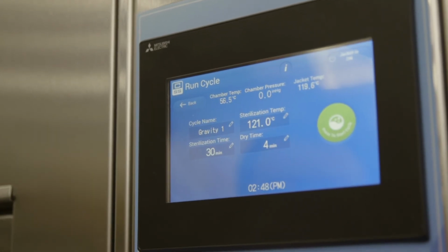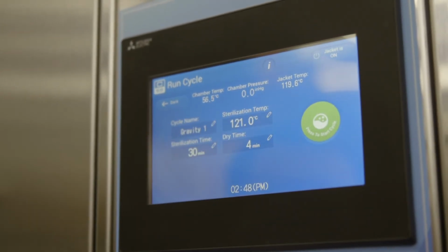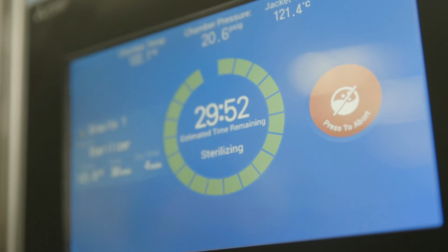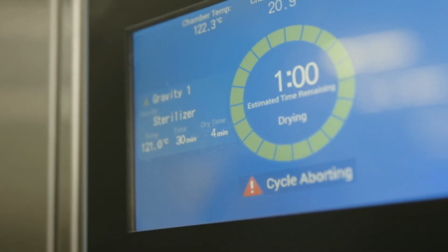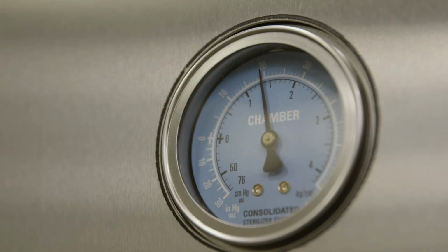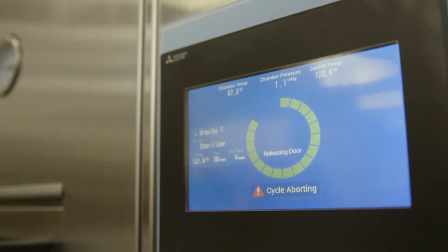Do not attempt to open the autoclave door once the cycle has started, as this presents a safety risk and could damage the autoclave. Should you suspect any issues with the autoclave, abort the cycle using the abort button on the touchscreen and wait for the temperature and pressure to return to a safe range before opening the door lock. Remember, the goods haven't been fully sterilized until they have gone through a successful sterilization cycle. Additionally, here is the liquid cycle.